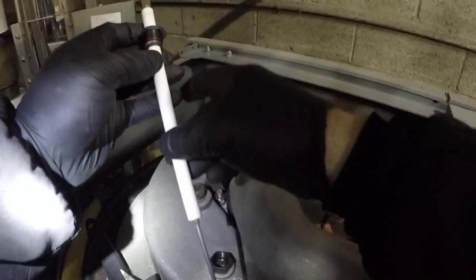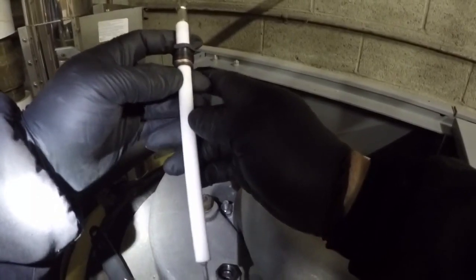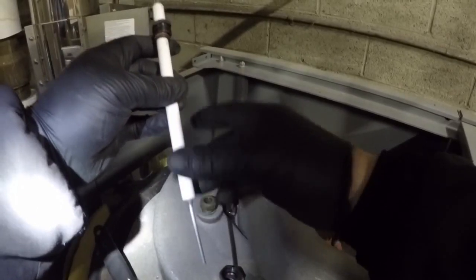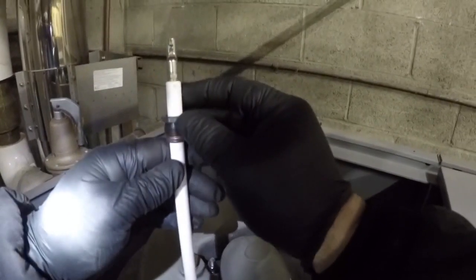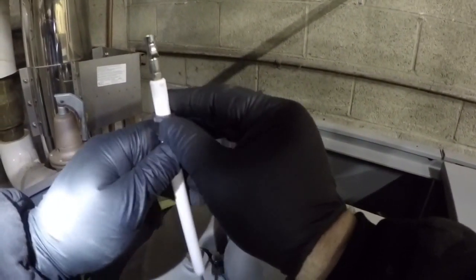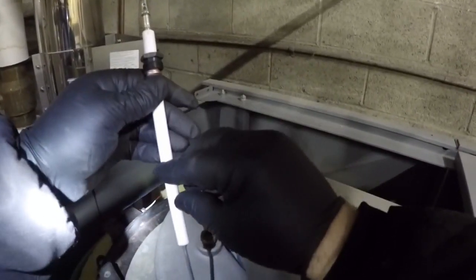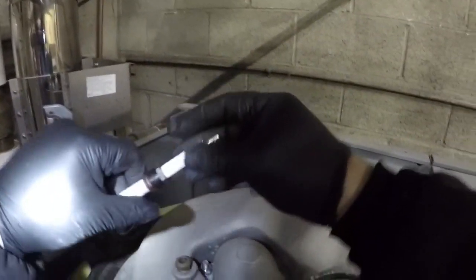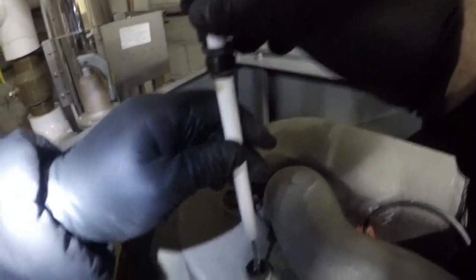We're all cleaned up now. We've gone over all the ceramic making sure we don't have a lot of cracks, hairline fractures, or flaws that are going to impede our operation. Making sure that we're in the right location — if we set it up here and leave this much sticking out, we'll end up outside of our flame area. Making sure everything here is nice and snug, so back on in.